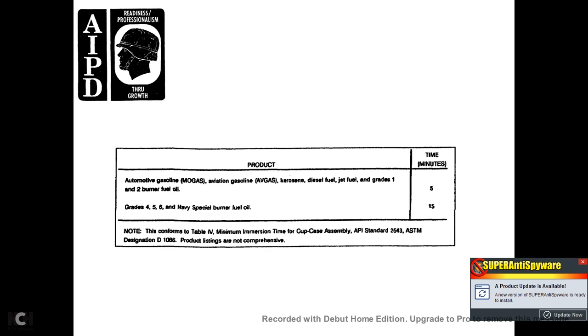Minimum immersion times (per API Standard 2543 / ASTM Designation D-1086): automotive gasoline, aviation gasoline, jet fuel, kerosene, diesel fuel, and grades 1 and 2 burner fuels require 5 minutes. Grades 4, 5, and 6 and Navy Special Burner Fuels require 15 minutes.